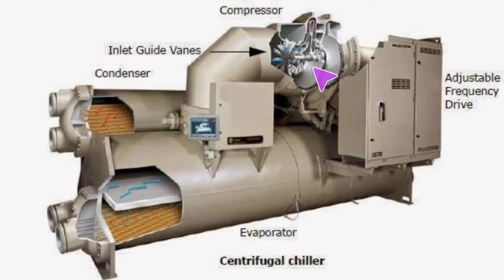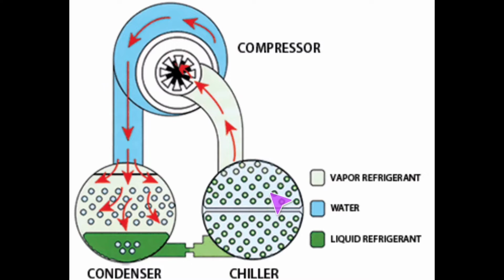But this is what controls the guide vanes, and there are 2 sets of vane controls in this machine. Just something to be aware of. I go through all this in person, on site, on the machine itself in that other video. Regardless, evaporator through the suction into the guide vanes, and then we start hitting the compressors. And from here, let's switch over to our next slide. So we'll take a couple of minutes and spend it right here.